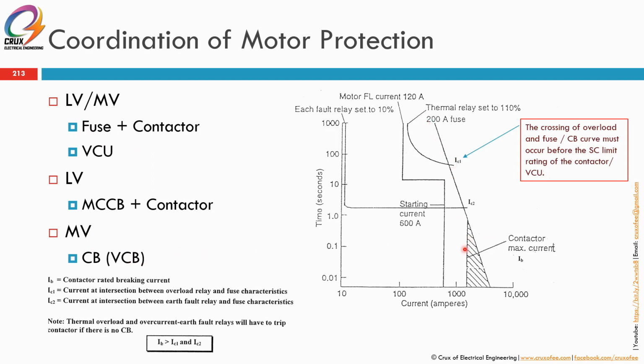So let's see here. Please note here, one is the overload curve, second is the fuse. So the fuse and the overload curve must cross over or occur before the short circuit limit rating of the contactor or the vacuum contactor unit. For example, so let's see, this is a 120 amp motor. So I'm guessing the contactor is using maybe 200 amps or 300 amps. Let's say the short circuit rating of the contactor is up to 10 times of the rated current.